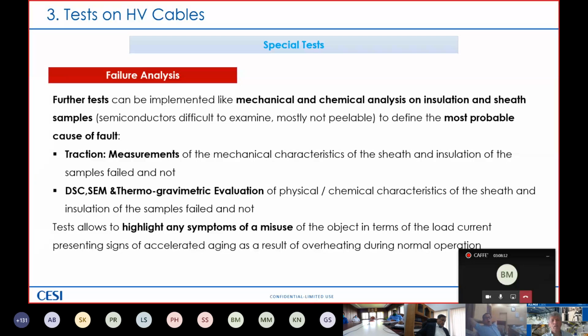Then differential scanning calorimetry, SEM, and thermogravimetric evaluation of physical and chemical characteristics of the sheath and insulation are performed on samples failed or not. And this allows us to highlight any symptoms of misuse, for example, accelerated aging due to overstress on the object in terms of load current, presenting signs, as I said, of accelerated aging as a result of overheating during normal operation.